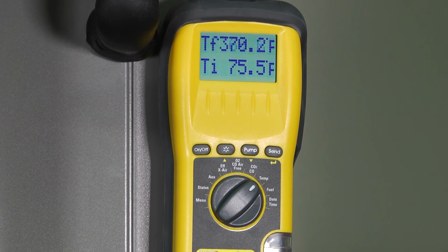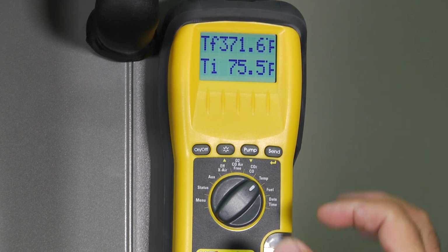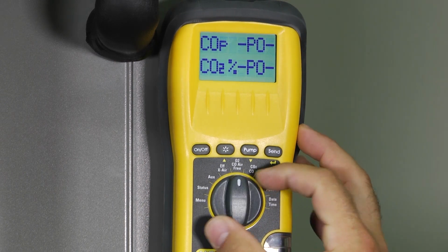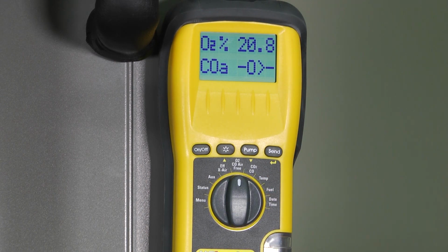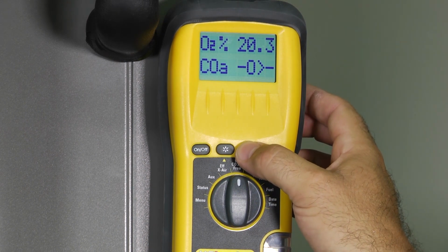I'm starting to climb up just a bit there that you can see. So really I've reached now what we call steady state. And that just means my heat exchanger's warmed up. It's actually doing what it's designed to do at this point. So now I can turn around and I can go over and look, and you can see my O2 is at 20.8, which is what our standard air is going to be inside my system.